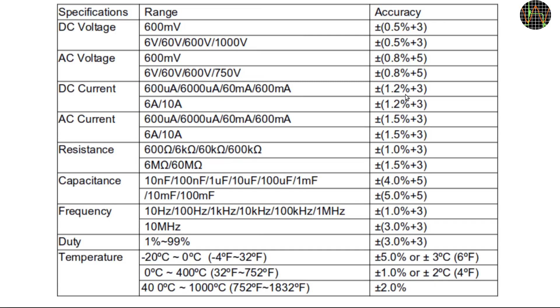For most of my tests, I compare the HT118 with a 6.5 digit Agilent 34401A. I could use my Solartron 7150P, which has a digit more, but it's a lot more cumbersome to remote control, and for verifying a 6000 count meter, the Agilent will be more than good enough. These tests are pretty boring to watch. Most of them run like this one, which verifies the DC voltage.